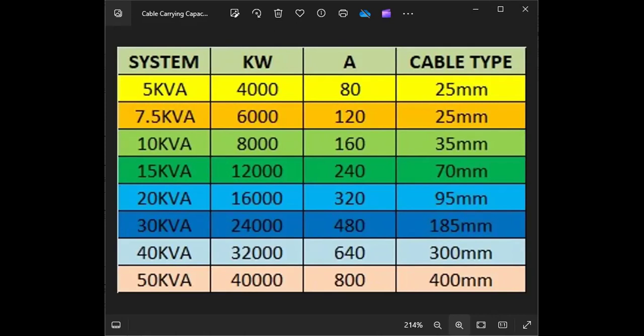Assuming now we are using a 5 kVA inverter system. We know that the maximum power a 5 kVA can deliver on peak load is 4,000 watts, or 4 kilowatts. That is by multiplying by 0.8, which is the power factor, to get the real power. 5 kVA is apparent power, but 4 kW is the real power. So at 4,000 watts, the maximum current is 80 amps, and a 25 mm cable can conveniently accommodate it.